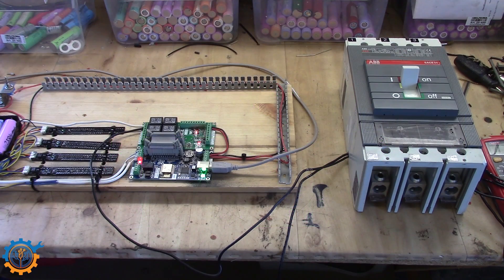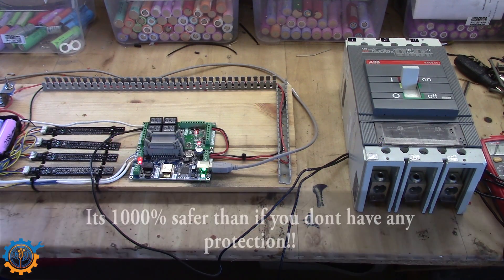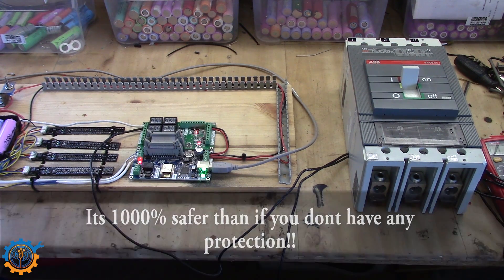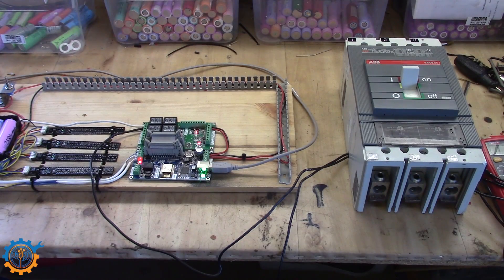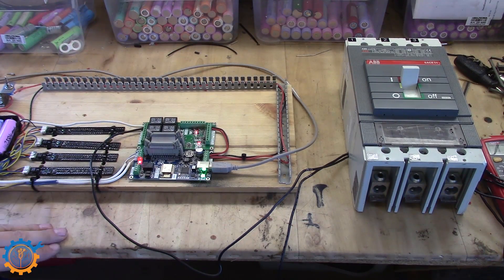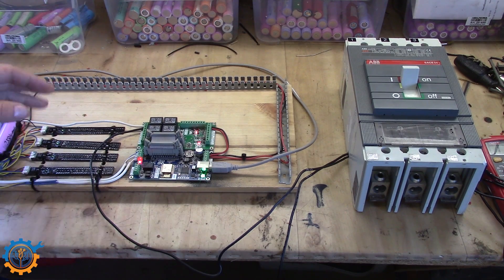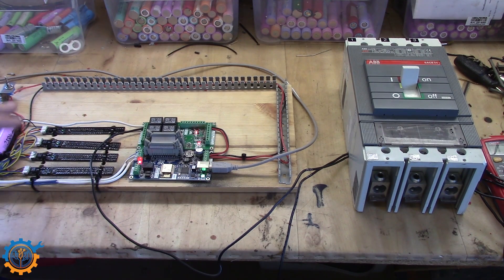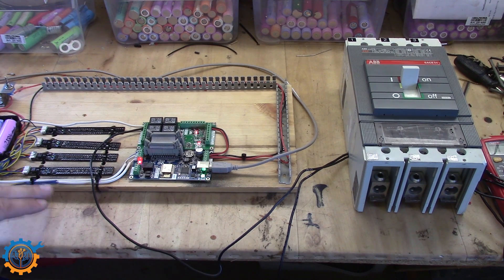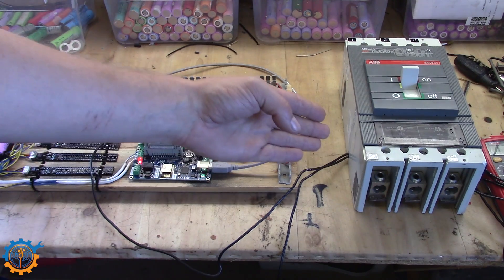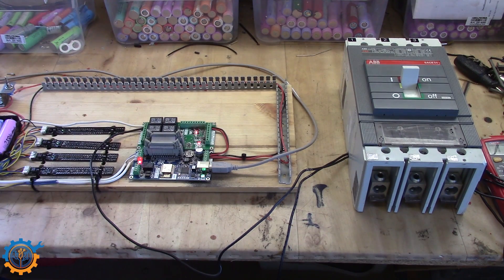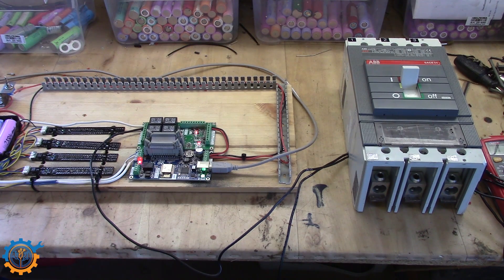Today's video was about how you can in the simplest way hook up a shunt trip to your watchmon system and breaker by just simply doing it this way. It's not the most optimal way and it's not the most safe way, but at least you have the basic protection. And if you get yourself a Batrium system, this is the first thing you should do. Yes, the Batrium will take care of balancing and reporting back to you guys, but what if you aren't at the computer? How do you protect the system? With a shunt trip like this and a watchmon hooked up, you can easily protect the system.